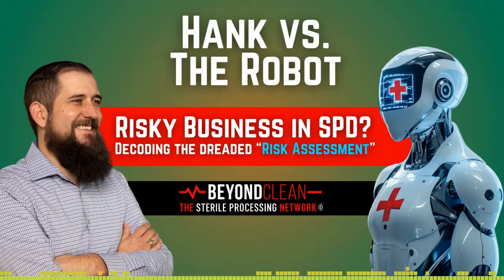Now, why would you conduct one? Here are a couple of examples. One, consistent wet packs. You notice multiple loads coming out of the sterilizer with wet packs. This could prompt a risk assessment to figure out what's causing the issue, the likelihood of contamination, and the impact on patient safety and compliance. Two, loaner instruments.